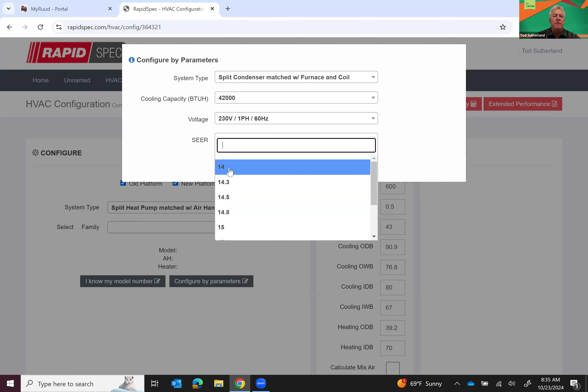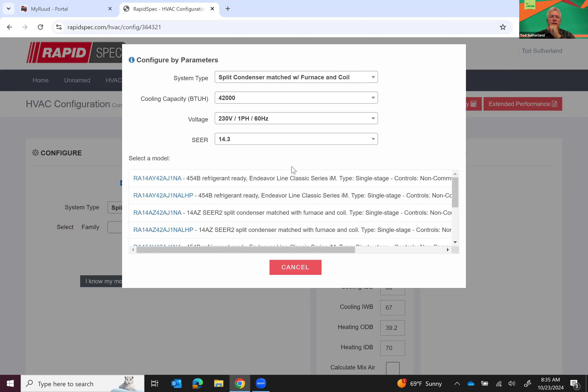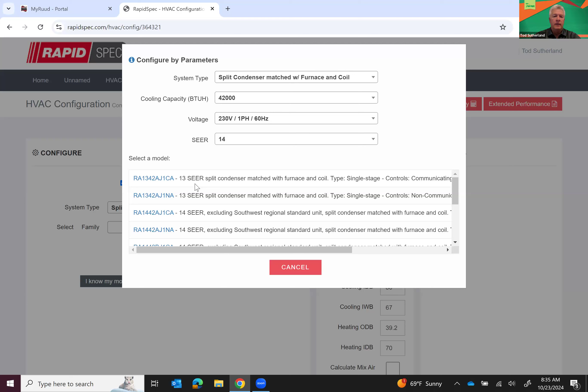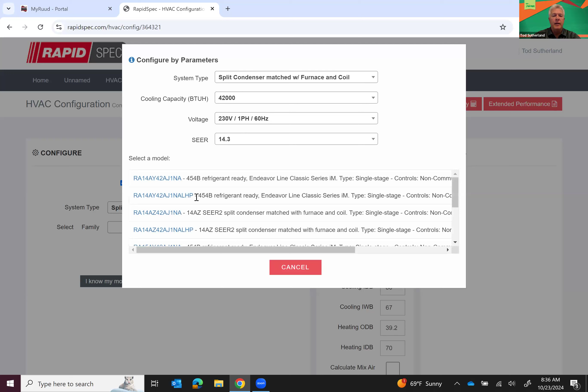We're hoping RAPIDSPEC will change some of this, because if I select 14 here, it's going to give me older SEER model numbers. Since I use RAPIDSPEC so much, I know I need to go to at least a 14.3 in order to see SEER 2 equipment. You'll see descriptions here when you select this, and if it says SEER, keep in mind you need SEER 2 equipment, so go to at least a 14.3 to see SEER 2 listed.